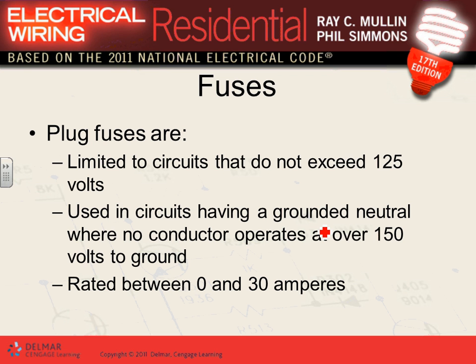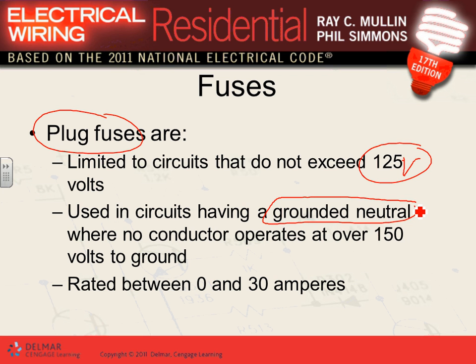Now, fuses. There are plug fuses — the little screw-in fuses. We use them typically to protect equipment like motors, and they're rated not to exceed 125 volts. They are used in a grounded system when the conductors are operating at not over 150 volts to ground, and the amps are limited to 30 amps.